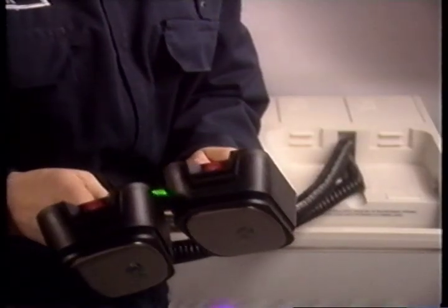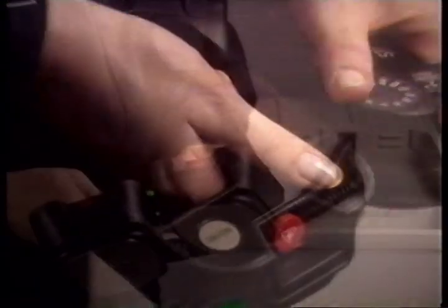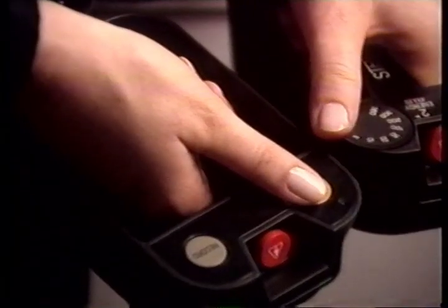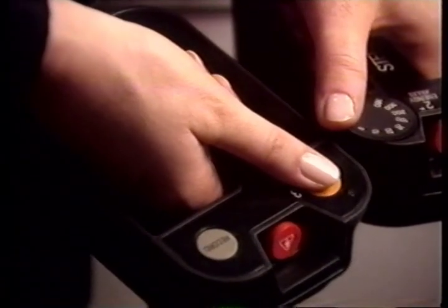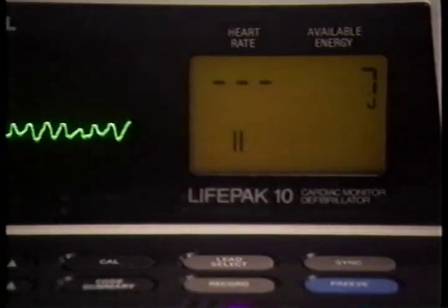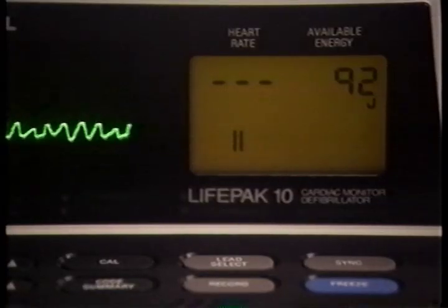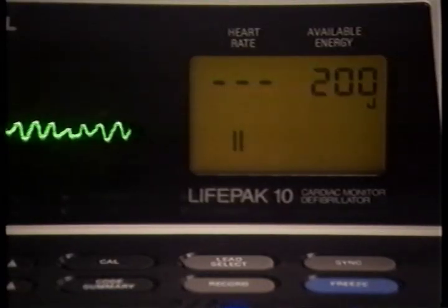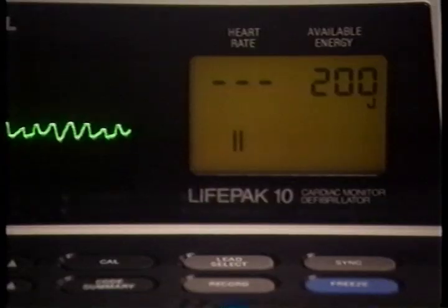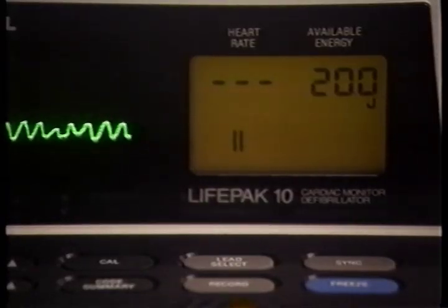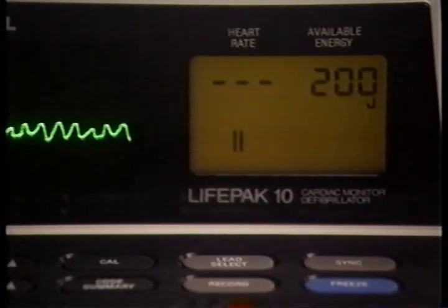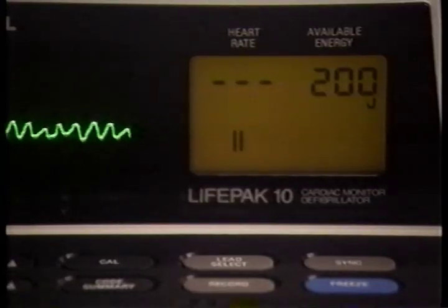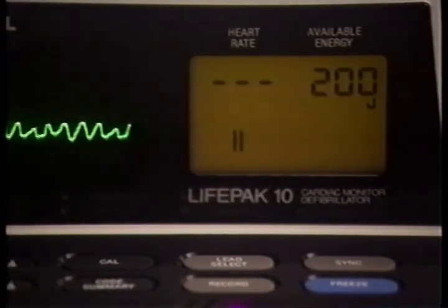Number 2, dial in the appropriate energy level on the top of the sternum paddle. Number 3, push the charge button on the apex paddle. A ramping tone will be heard as the LIFEPAK 10 charges up and the charge light will blink. The energy available meter on the status display will scroll up to the selected energy level. Once the LIFEPAK 10 is fully charged, a brief tone will sound and the light will hold steady.